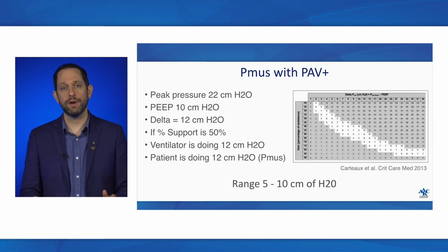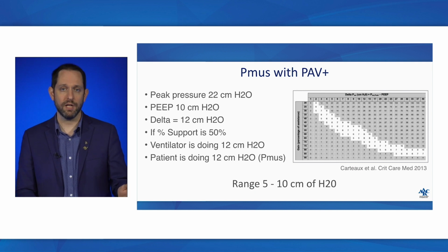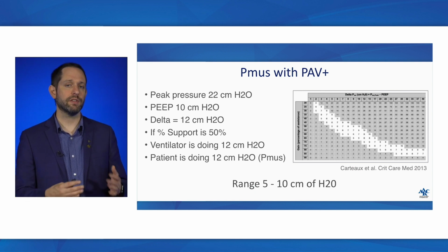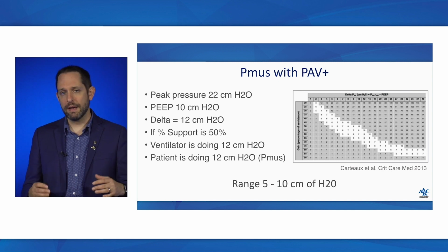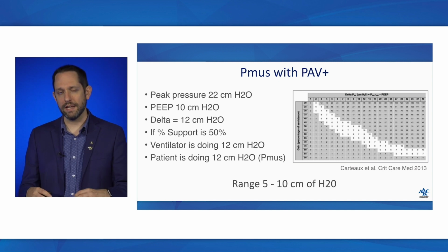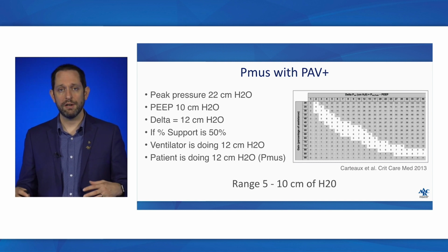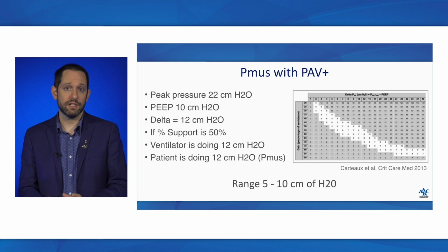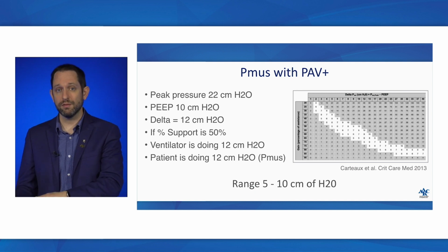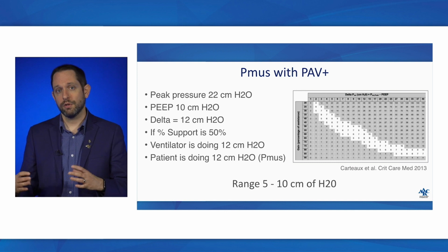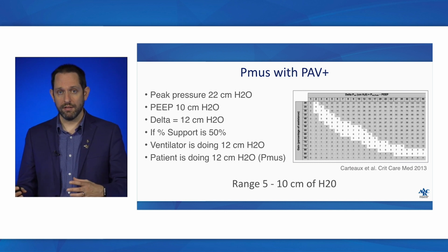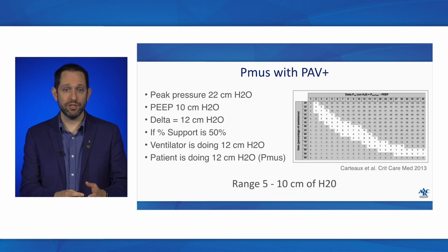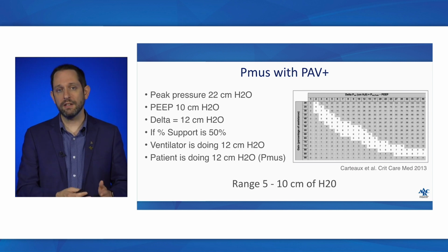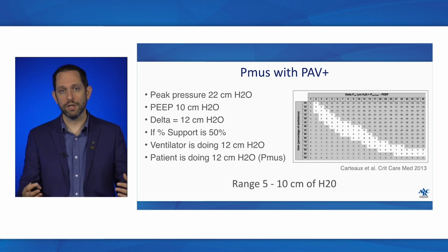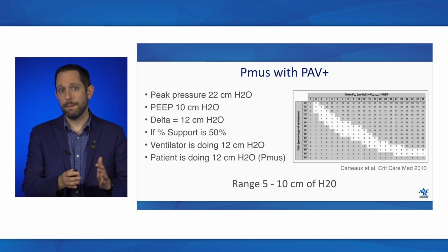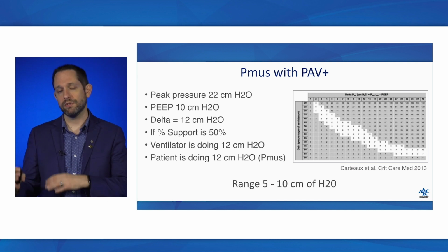Another way to estimate inspiratory effort is by measuring PMUS using the mode PAV+. You can measure PMUS with catheter placement, etc., but the mode PAV+ automatically calculates compliance and resistance and uses that to put into the equation of motion. And for breathing, this is basically taking the elastic load that is required to breathe and the resistive load, and these two things together create the total work required to breathe. And the muscular pressure generated by the patient is the PMUS. Now, when we place a patient on a ventilator, the ventilator shares some of the total work. So now the work is partly from the ventilator, partly from the patient to overcome the elastic and resistive loads.